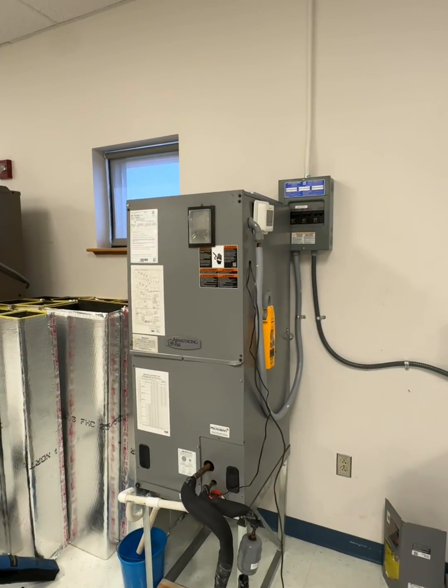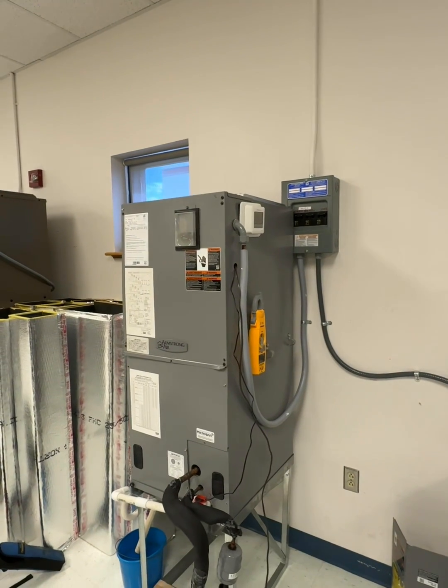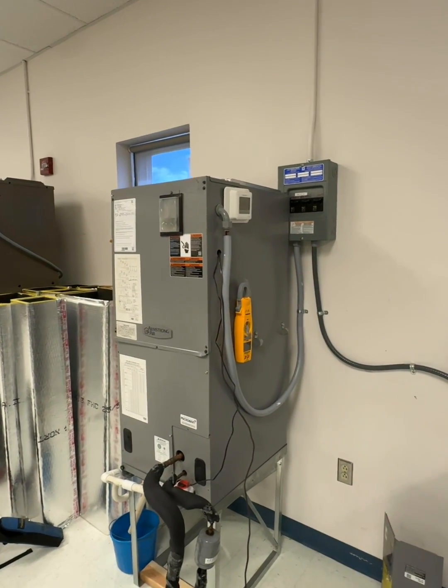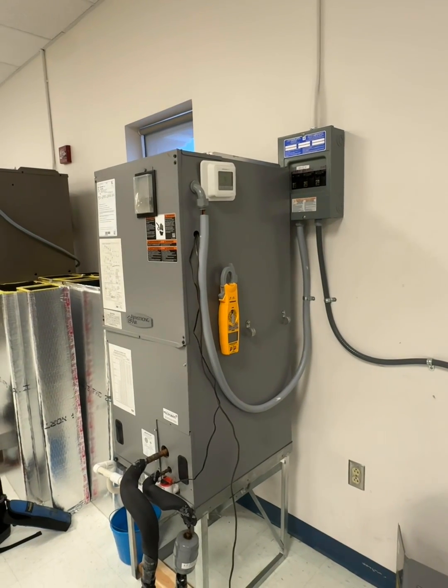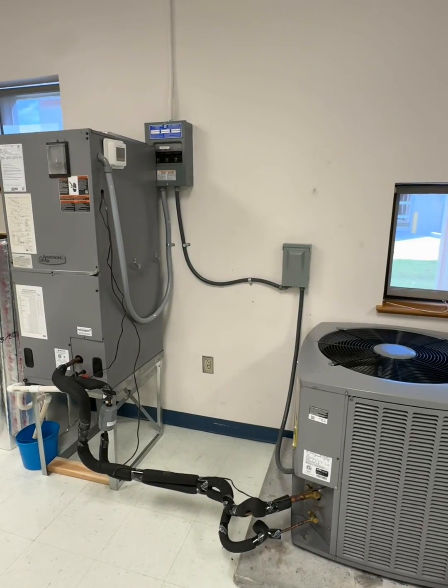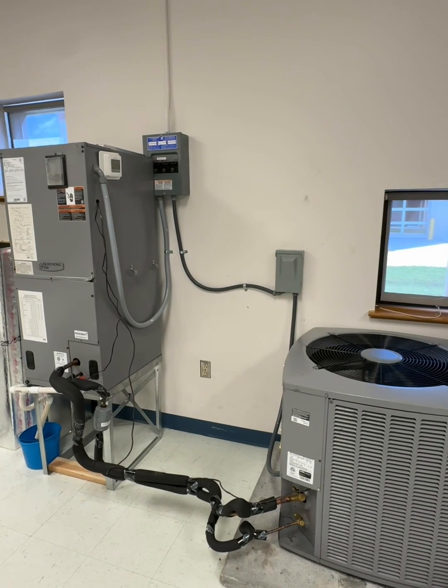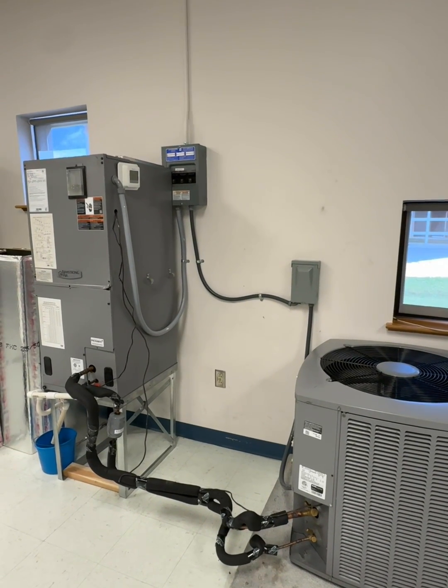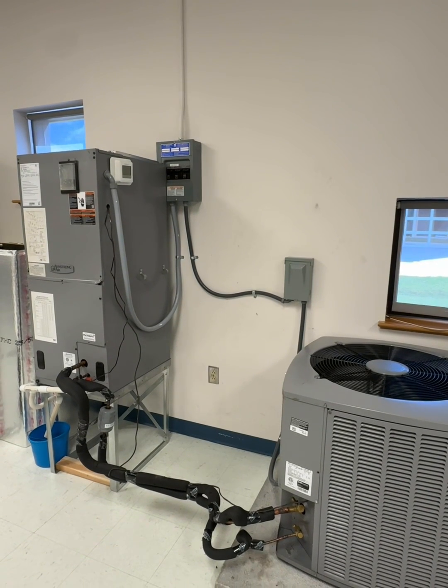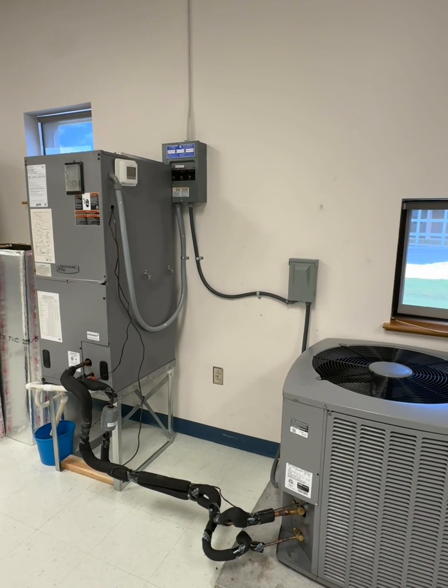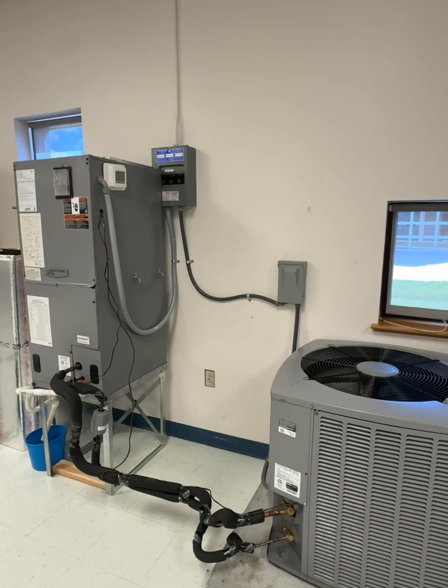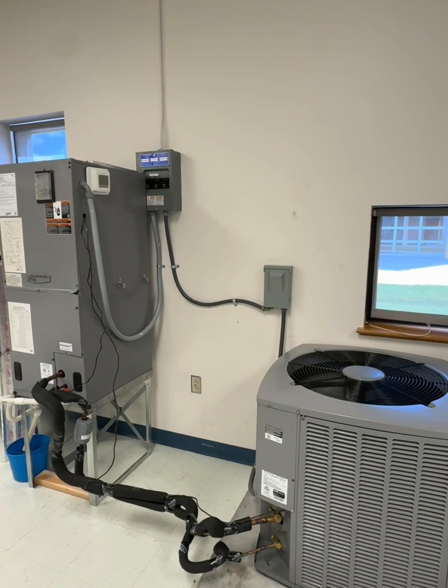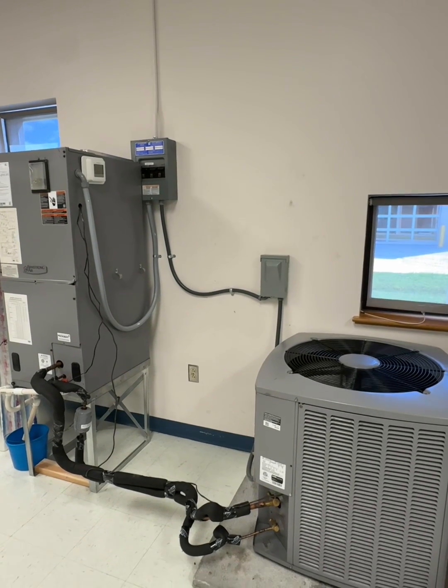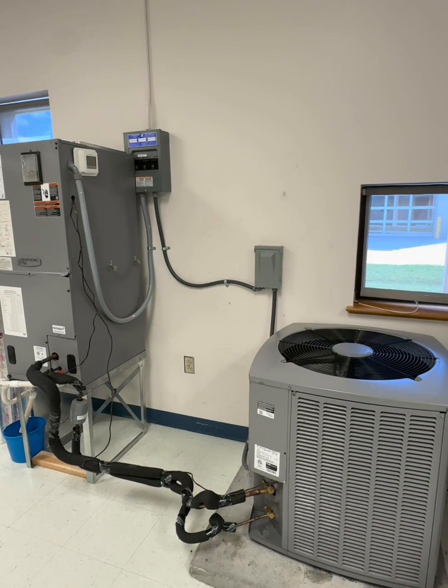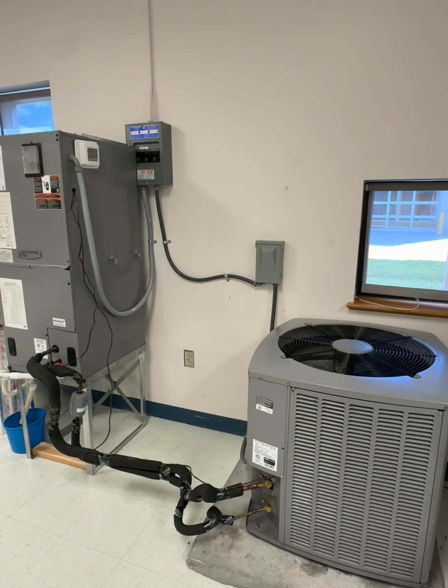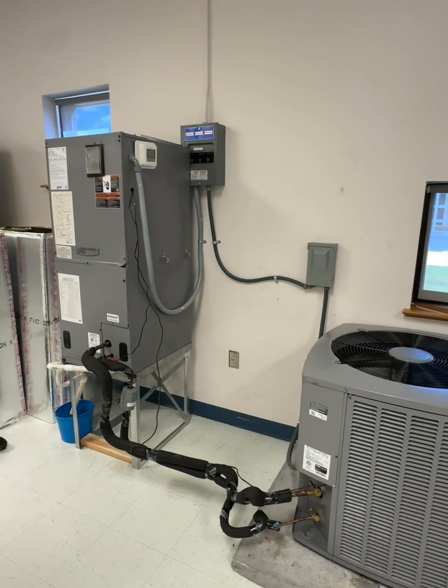The air filter in a split system has two jobs. The first is to protect the equipment. It prevents dust and debris from being pulled into the evaporator coil, blower wheel, and ductwork. Without a filter, dirt will build up on the evaporator coil, reducing heat transfer, restricting airflow, and eventually causing freeze-ups or compressor damage. The air filter also improves indoor air quality. It removes airborne particles like dust, pollen, and pet dander from the air that circulates through the system. This helps create a cleaner, healthier indoor environment.